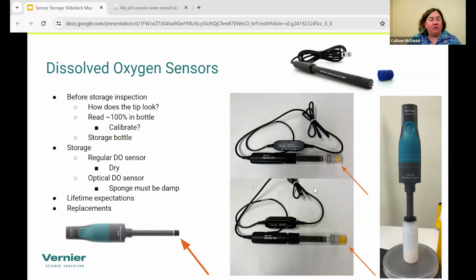And we do have all the replacements for the tips. For the LabQuest version of the optical dissolved oxygen sensor, it involves a tip and a little SD card that you have to put into the switch box. For the Go Direct version, you just have to replace the tip, and then there's a little calibration code that you enter on the back end of the software, and we have instructions for how to do that.